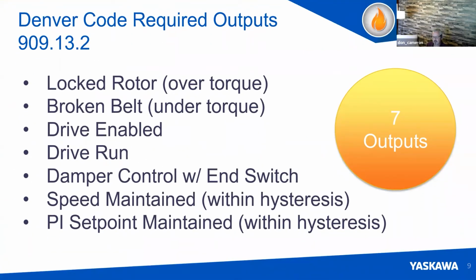So unique to Denver code, which I believe, don't quote me exactly, but I think it's 909.13.2, are some common outputs that are not necessarily always used all the time, but for the Denver fire mode, the drive is required to output back to the fire control panel lock rotor, which is an over torque situation. So if the motor shaft is jammed, or a broken belt, so it's not drawing enough current, it says, hey, I'm running at full speed, but I have no torque. That's a problem. Is the drive running? Is it enabled? Is the damper end switch closed? Is the speed being maintained? And is the PI set point being maintained? So it's a total of 7 outputs that are required by the Denver code, which is more than most.